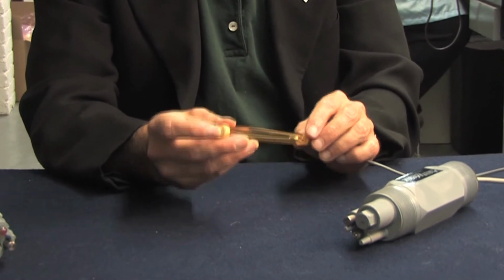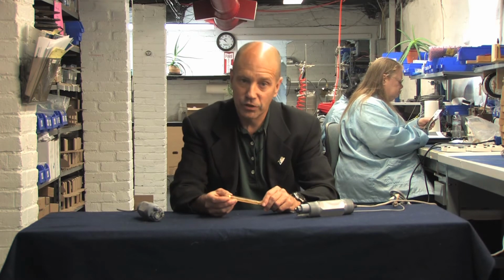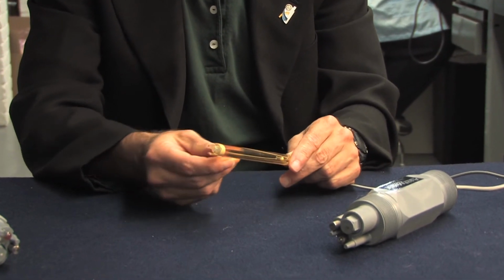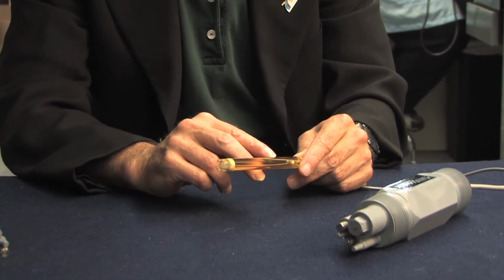The process electrode and reference electrode are combined into one circuit in one glass envelope, hence the term combination. A porous junction allows electrons to flow from one electrode to the other, thus completing the circuit. This makes for a pH or ORP probe that is compact and inexpensive, but there are limitations to this design. The porous junction that completes the electrical circuit allows dissolved matter to flow into the glass enclosure in the salt solution. The result is that the silver wire becomes coated and the fill solution becomes contaminated. This causes the efficiency of the probe to decline over time. Usually after a year or two, the probe's efficiency is so low that the user throws out the probe.